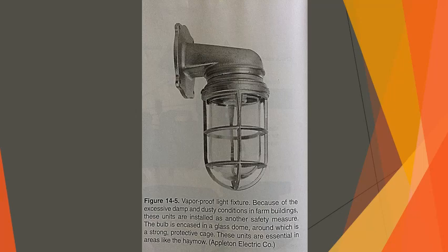Poultry house, hog barn, sheep house, and horse barn. These buildings must be well electrified, although the electrical demand for these buildings is much less than that of the dairy barn. Lighting should be plentiful. One light for every 150 square feet of floor area is suitable. Wall switches or wall switch lights are advisable. Timer switches to increase egg production should be a part of the lighting circuits of the poultry house. Receptacles should be located every 12 to 15 feet along the walls and mounted no lower than 5 feet above the floor.